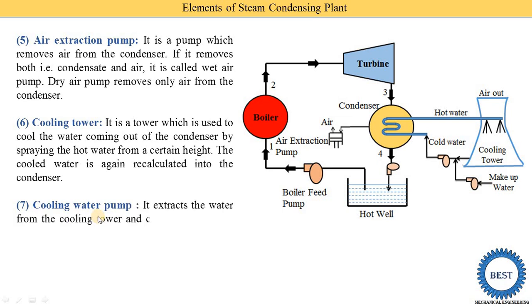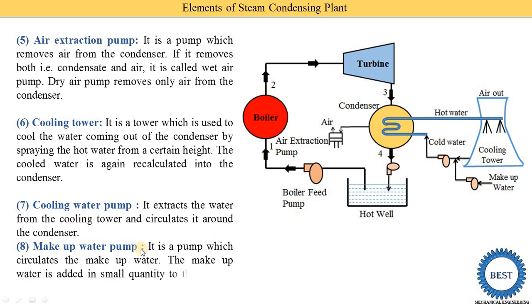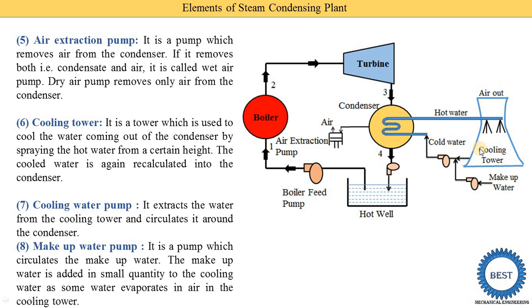The next component is the cooling water pump. It extracts the water from the cooling towers and circulates it around the condenser, transferring water from the cooling towers to the condenser. The last component is the makeup water pump. We need to add makeup water because during the cooling of water in the cooling tower, some quantity of water is evaporated. So we add fresh water, called makeup water, using the makeup water pump.